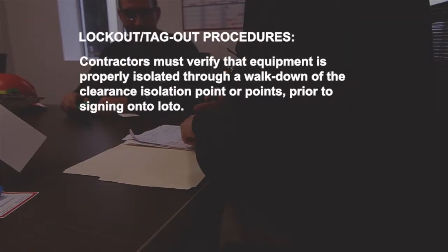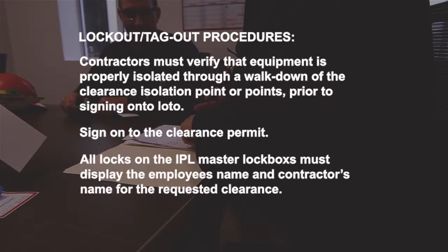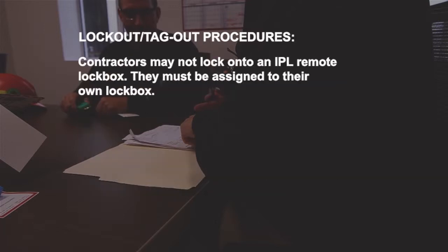Contractors must verify the equipment is properly isolated through a walk-down of the clearance isolation point or points prior to signing on to LOTO. Sign on to the clearance permit. All locks on the IPL master lock boxes must display the employee's name and contractor's name for the requested clearance. Contractors may not lock onto an IPL remote lockbox. They must be assigned to their own lockbox.